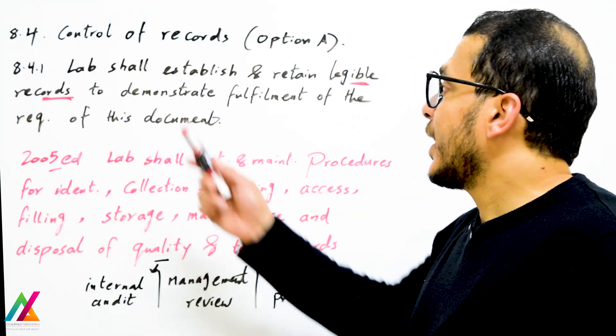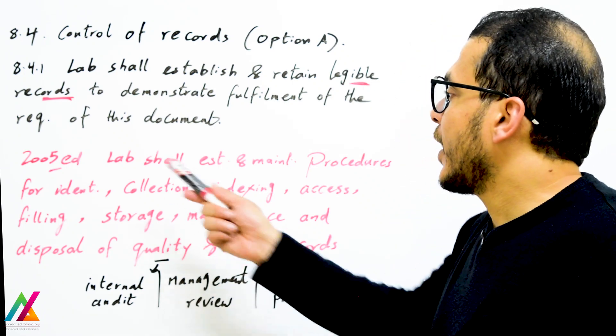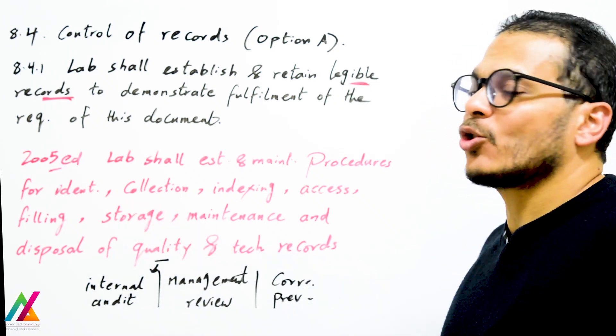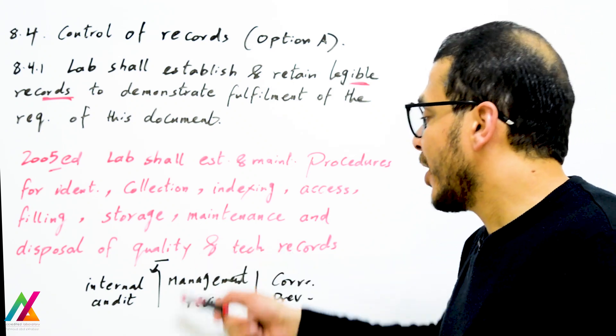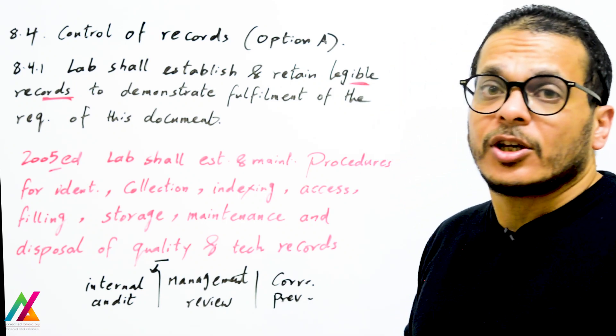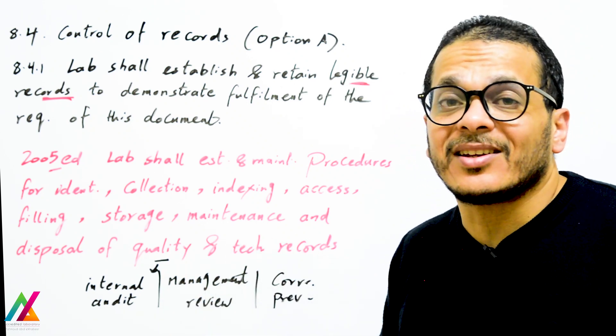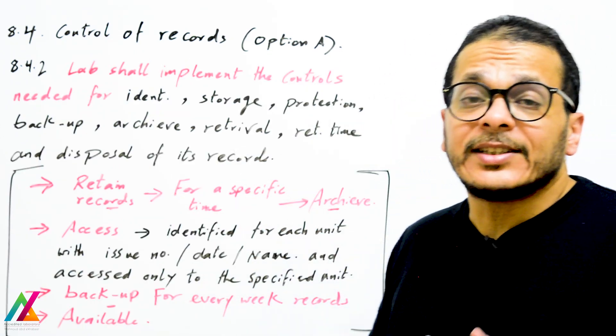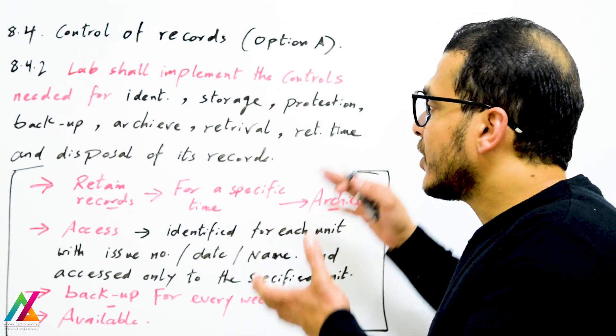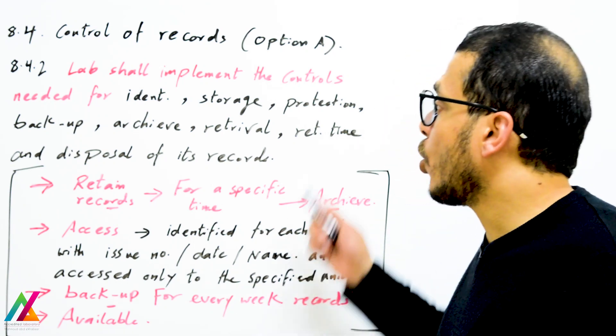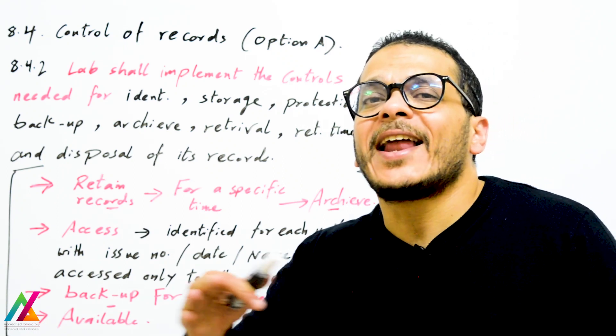The first requirement is that the lab shall establish and retain legible records to demonstrate fulfillment of the requirements. In the 2005 edition, the lab was required to establish and maintain procedures for identification, collection, indexing, access, filing, storage, maintenance, and disposal of quality and technical records. In 2017, this is more flexible — there is no mandatory requirement to prepare a specific procedure for retaining records.